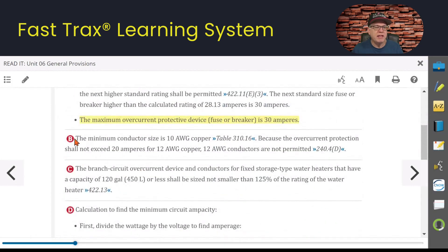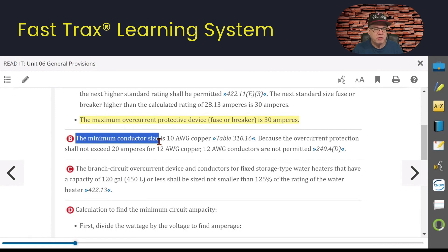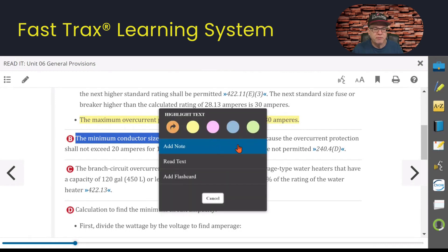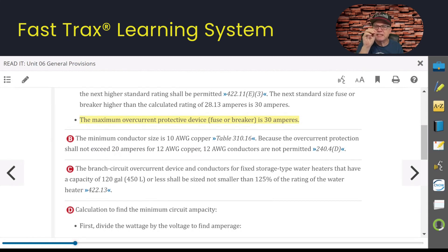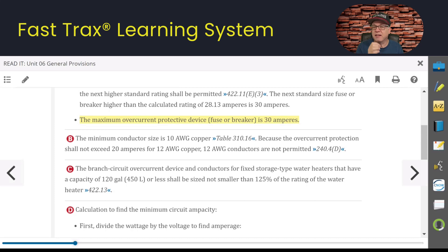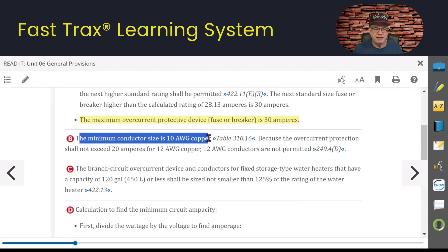What is the minimum conductor size? It is 10 AWG. If you go to Table 310.16, you'll see a little asterisk beside 12 gauge, which sends you to 240.4(D) — the small conductor rules. The overcurrent protection cannot exceed 20 amperes for a 12 AWG conductor. Since we have a 30-amp overcurrent device, the small conductor rules require at least 10 AWG. So based on the overcurrent device size, the minimum conductor size is 10 AWG.